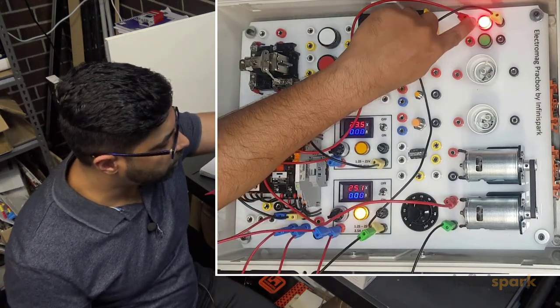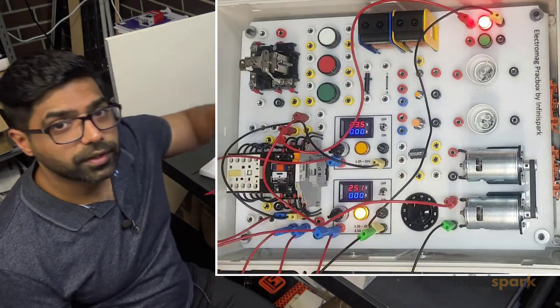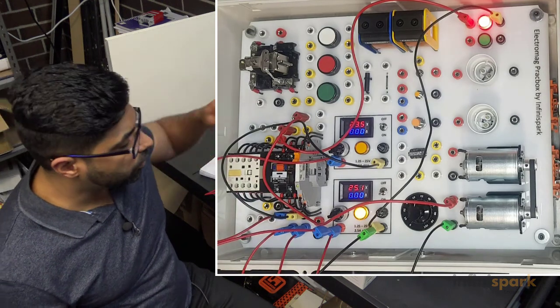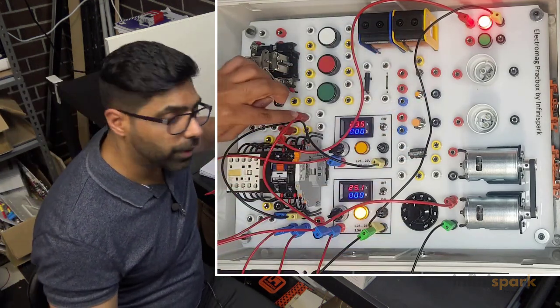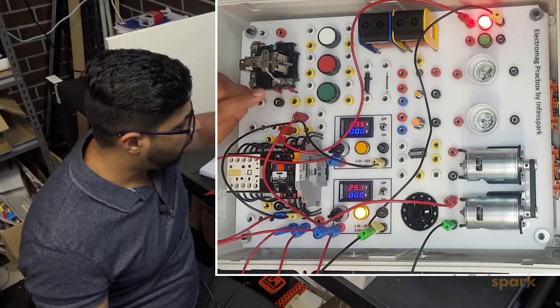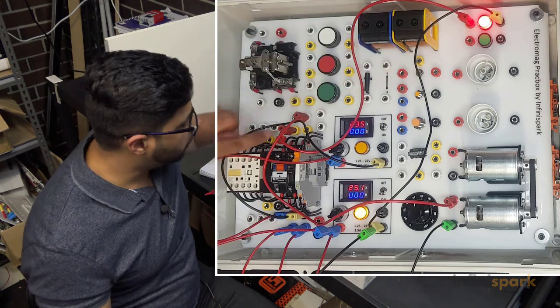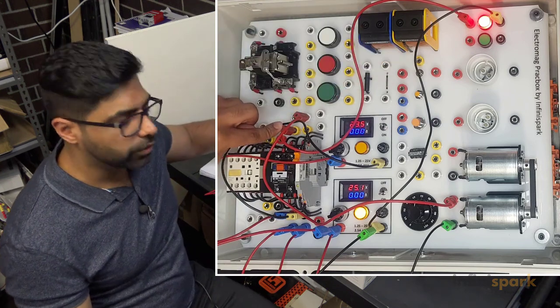You see how that light is still on, but the motor didn't turn on because the motor is going through the normally open side and that lamp is coming through the normally closed side.